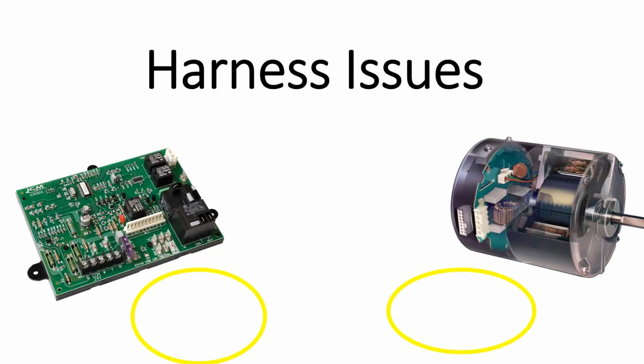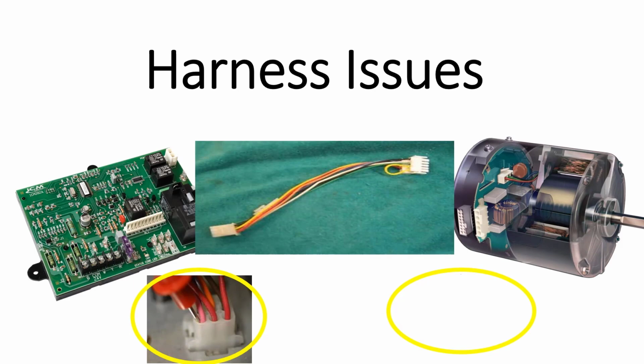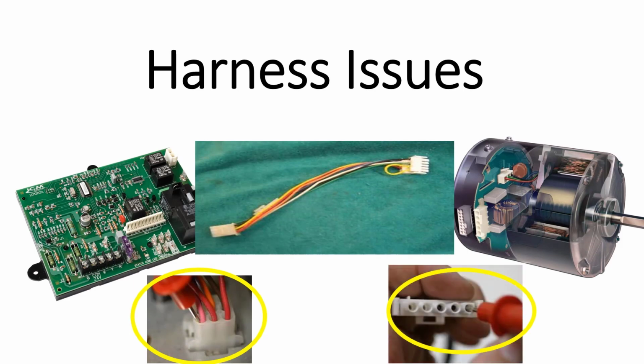In your ECM motor troubleshooting, one thing you don't want to overlook is the wiring harness. Most often the wiring harness is the problem that causes an ECM motor not to run. Because of shoving fat probes into the wires and damaging the contacts, many times the signal coming from the board to the motor does not get there. And the problem is the wiring harness.